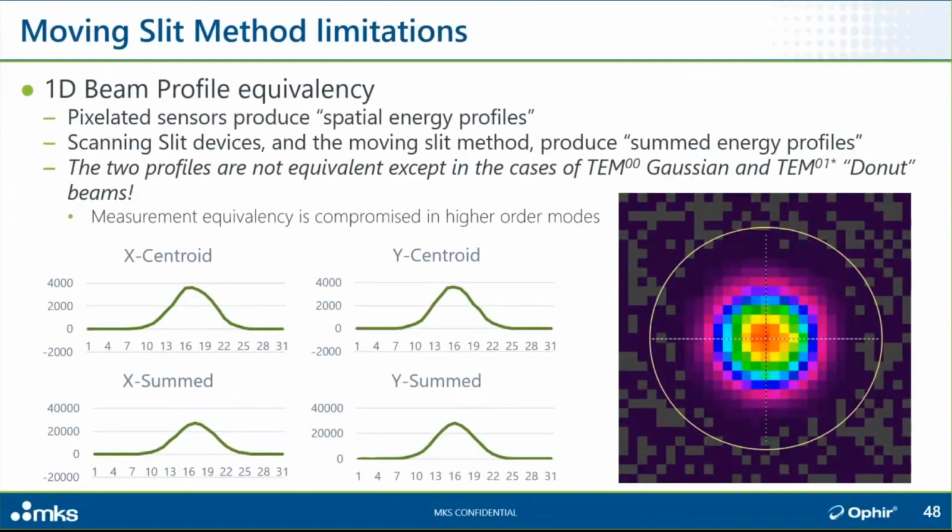So if you are doing any sort of comparison, if you've been using a scanning slit profile and want to go to a camera-based system, this is a really important distinction to understand, that the two are not necessarily comparable. You have to be very careful about how you compare those two sets of results.